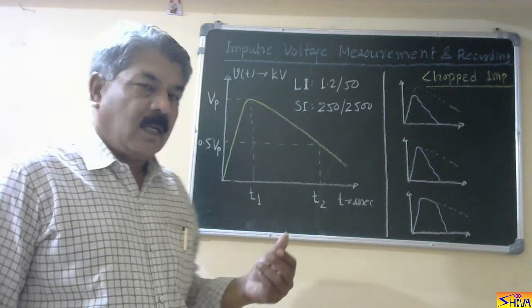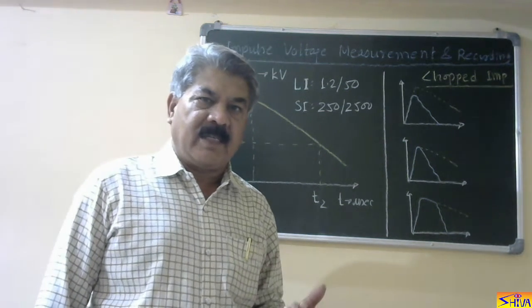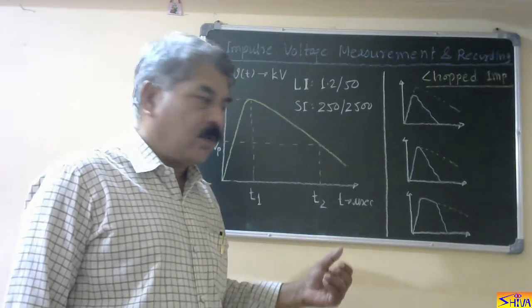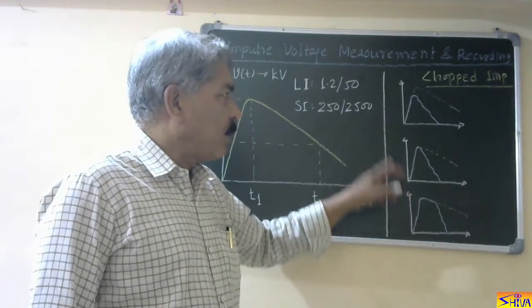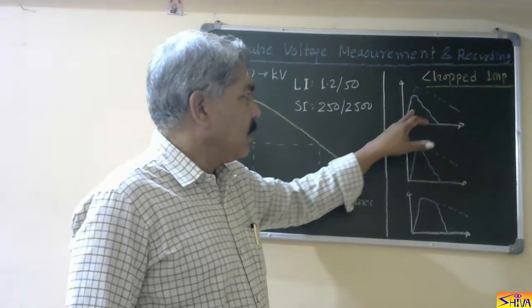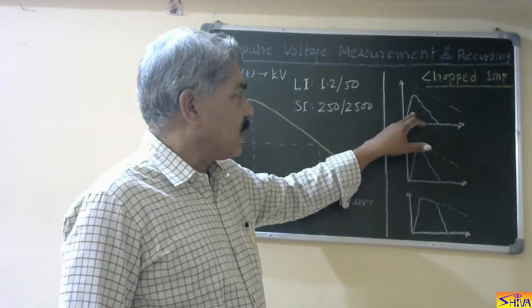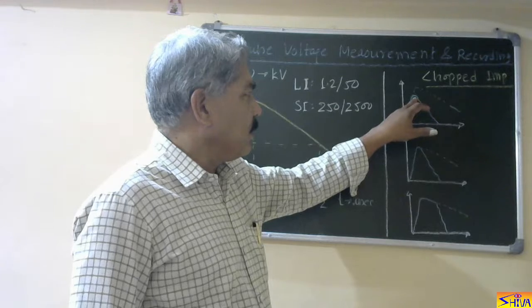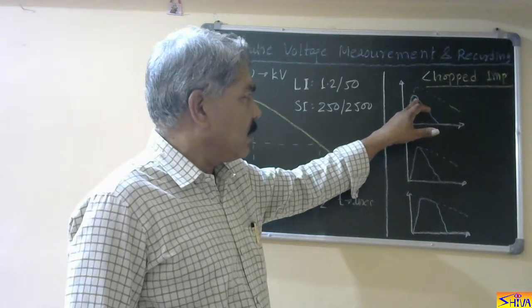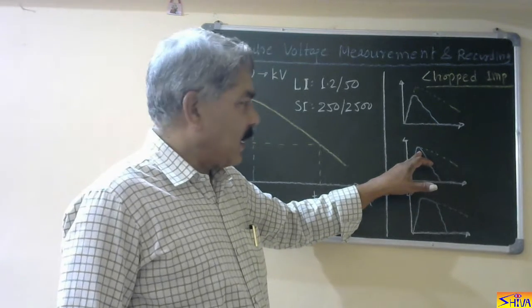Next thing is, if flash over, spark over, or the breakdown of the test object takes place, then this impulse voltage is chopped down. Here I have shown the chopped impulse. This is the impulse shown by dotted line. The breakdown or flash over or spark over of the test object has taken place at the rising portion. So when flash over or spark over takes place, the voltage collapses. Here, the same thing has occurred at the peak of the wave.